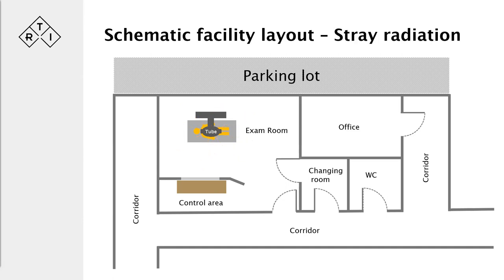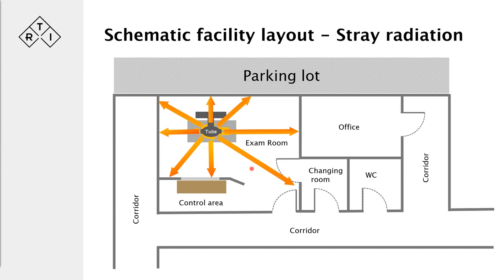On a normal exposure, both scatter and leakage are generated. These two types of unwanted radiation are areas of concern. From a radiation protection and safety point of view, they may affect adjacent areas to the X-ray rooms. To ensure safe operations, radiation limits have been established and are actually similar in many markets.